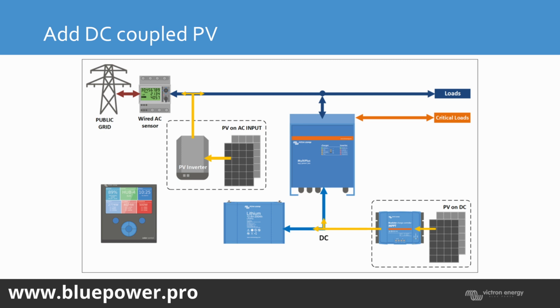And the Victron MPPTs require a voltage source to start charging, so they're not going to be able to recover the battery. So you're going to have to get a generator on site, connect it on the input, and then switch the inverters on. It's going to be the only way to recover it. So it's very important to make sure that you set your disconnect voltages on the system, so that it doesn't drain the battery beyond the point where you can't switch on again.